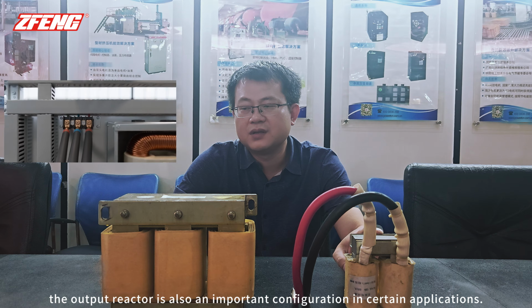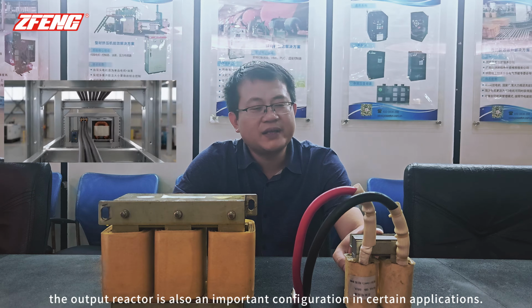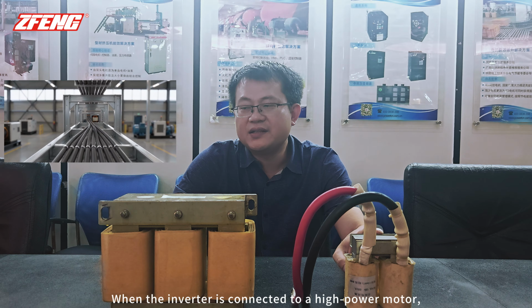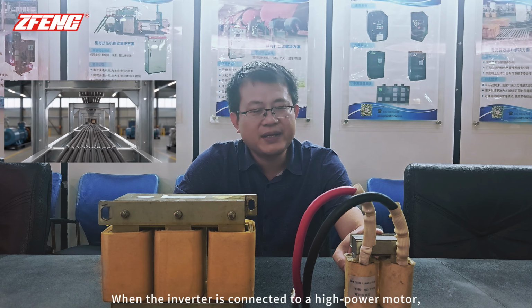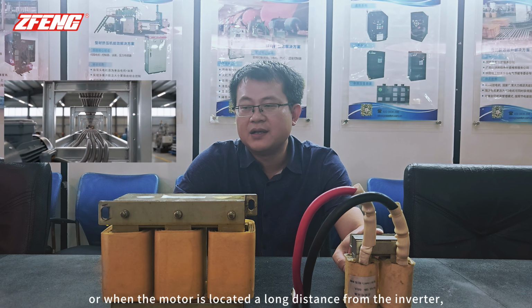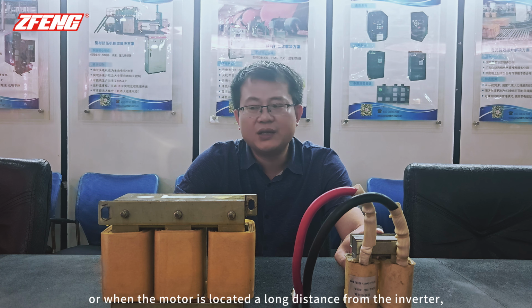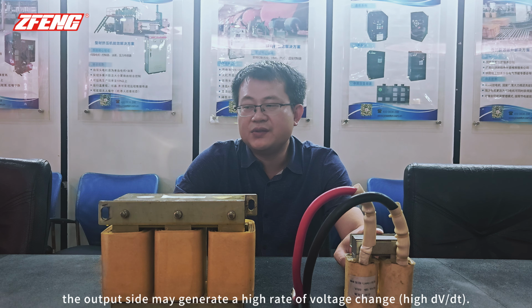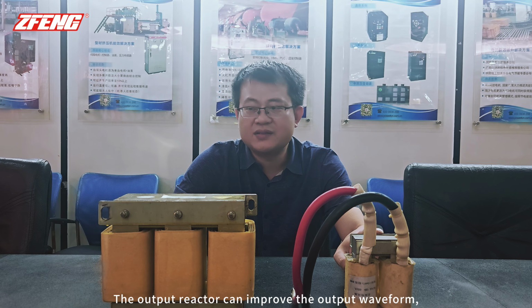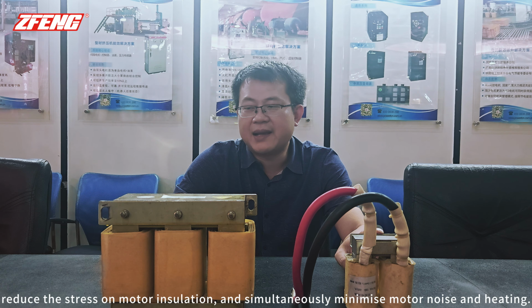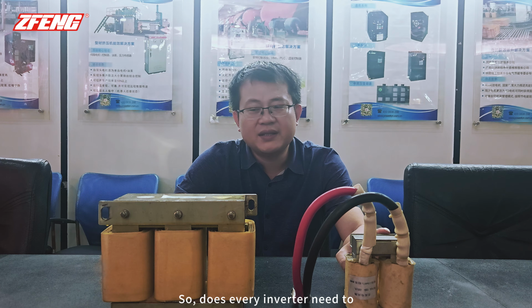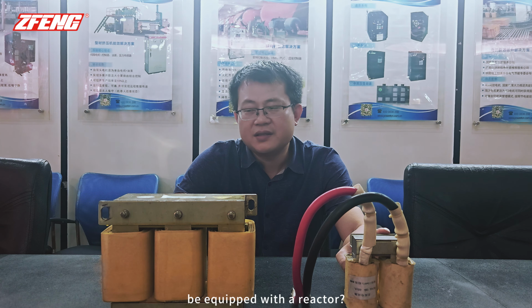The output reactor is important when the inverter is connected to a high-power motor, or when the motor is located a long distance from the inverter. The output side may generate a high voltage change rate, high dV/dt. The output reactor can improve the output waveform, reduce the stress on motor insulation, and simultaneously minimize motor noise and heating. So, does every inverter need to be equipped with a reactor?